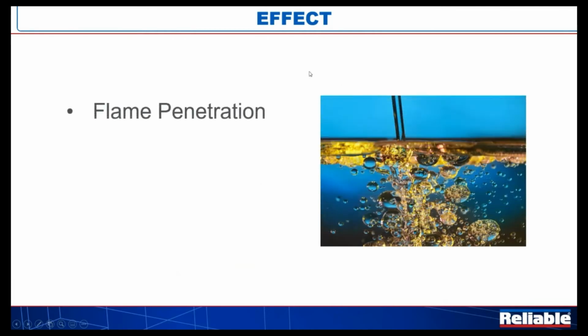And so what effect is this having on the fire? The large coarse water drops provide penetration down through the rising fire plume, and because they're under high velocity, they're hitting the surface in close proximity. They're actually creating turbulence in the surface of the fuel. And the water is what they call emulsifying. It's mixing together, and it extracts the heat, and it dilutes that fuel down, and that's part of the firefighting process, what they call emulsification, the blending of the two together, even for the period of time that it's being hit with the turbulence to affect that fire protection.